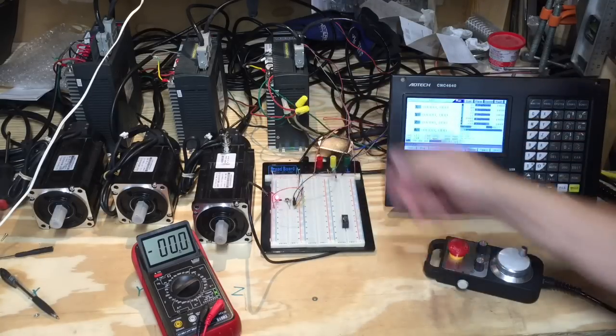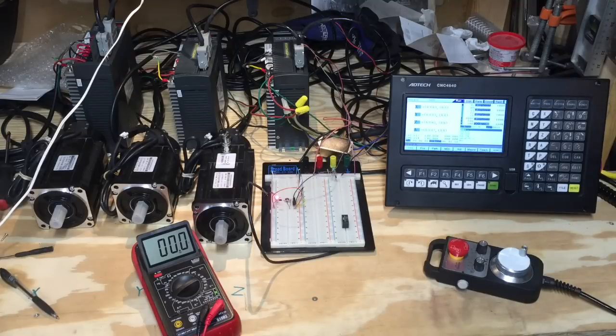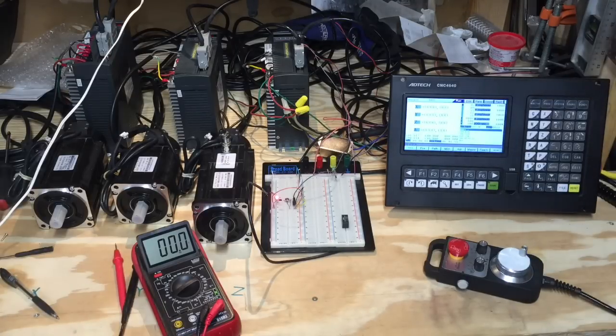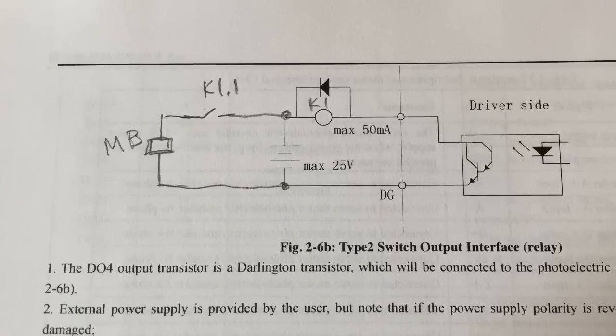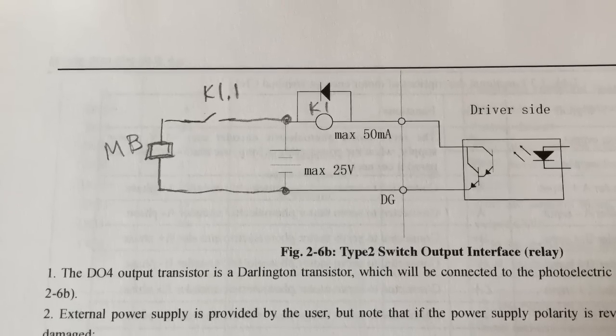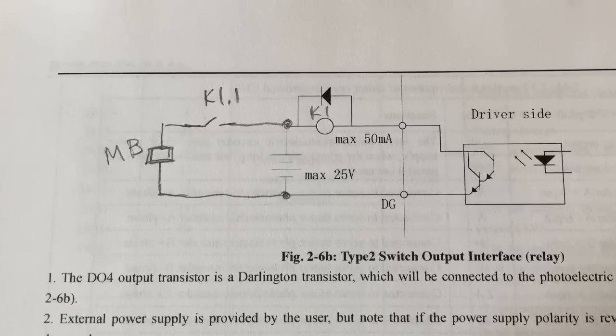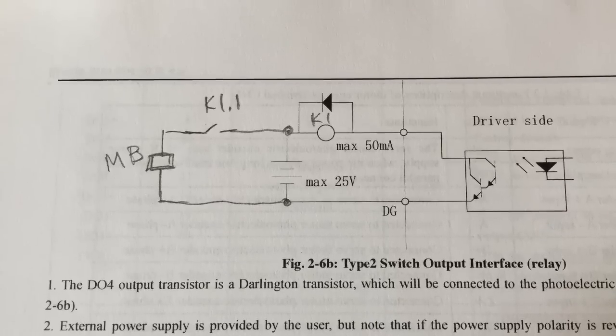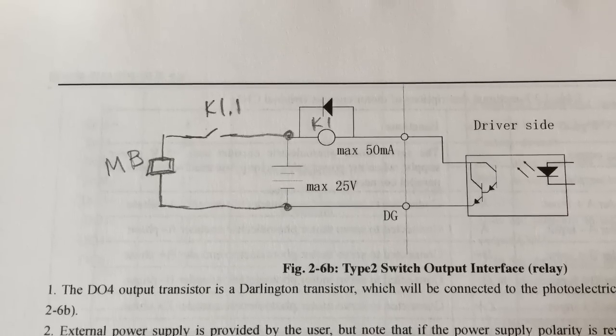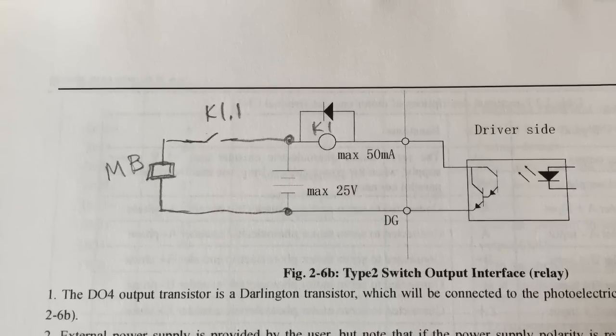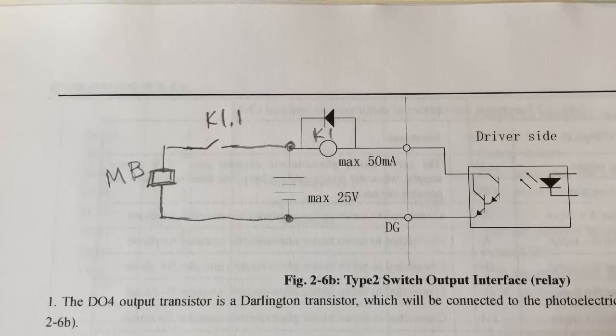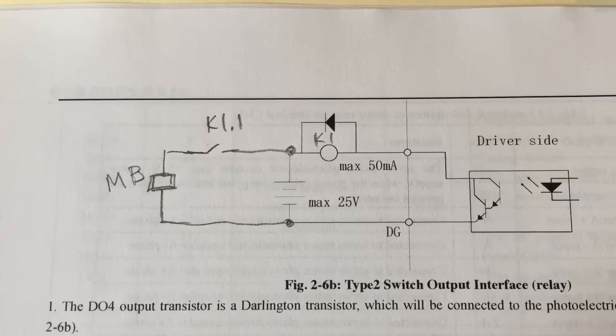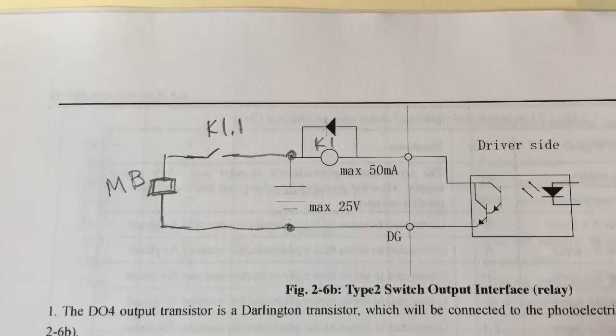So I decided to go with the diagram suggested by the manual for the servo drive. It powers the coil of a relay which activates the motor brake. In parallel with the K1 coil of the relay, we see the diode connected. These diodes are called flyback or shunt diodes.